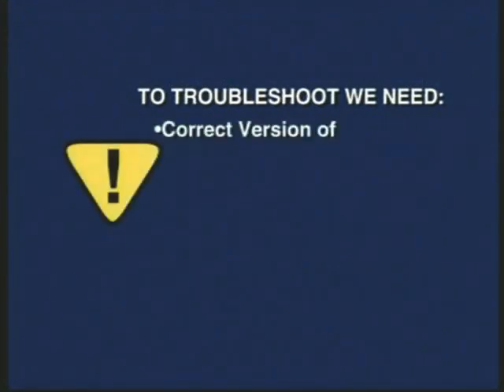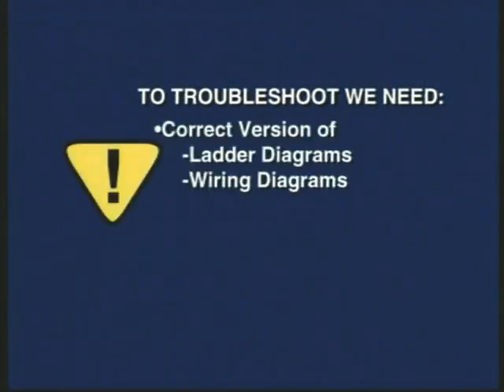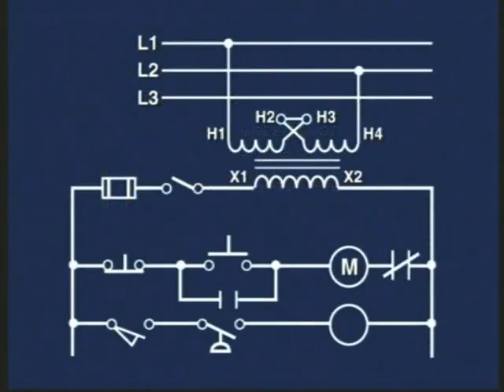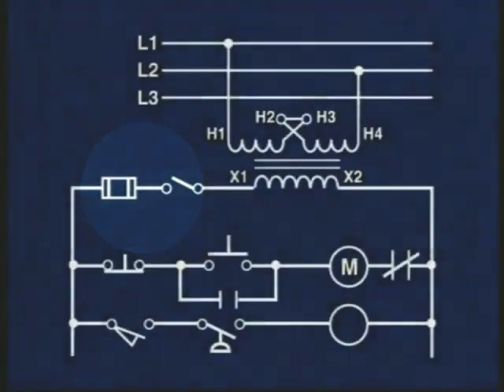First of all, we need to have an updated and correct version of ladder diagrams, wiring diagrams, and of the layout of components in the enclosure, including the terminal locations which are connected to devices. If we don't start by having this, our task will be much more difficult, perhaps by a factor of 100 or more. It is better to identify the area in which a problem may have occurred or where the symptoms seem to be. This, in turn, could give us further direction into finding the problem.